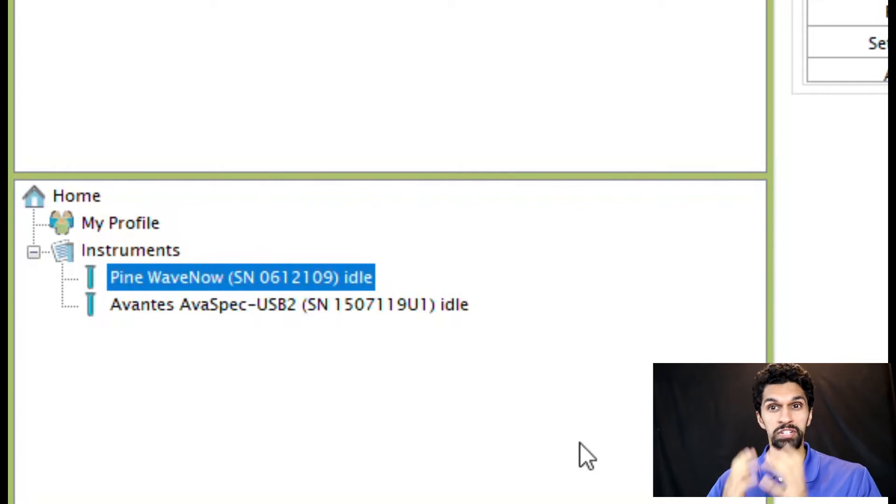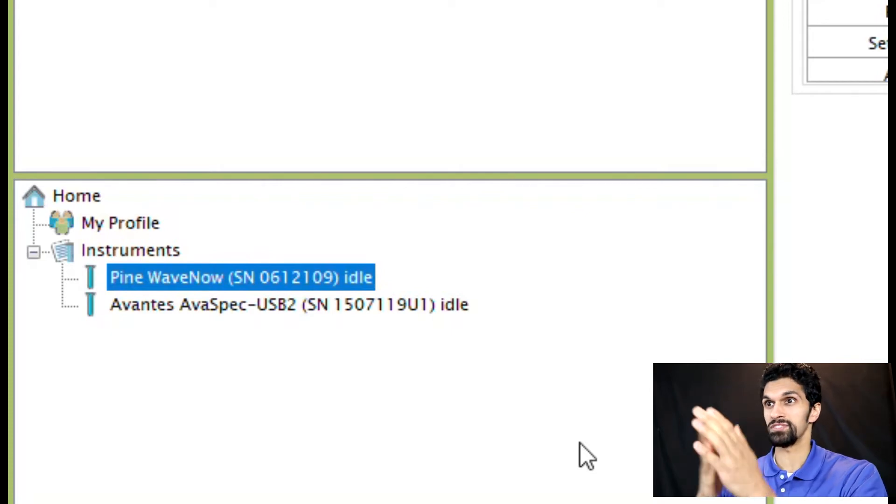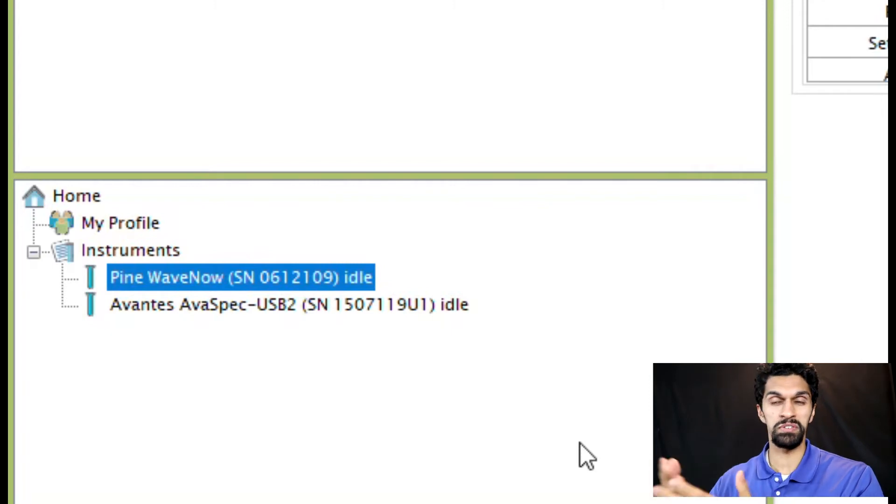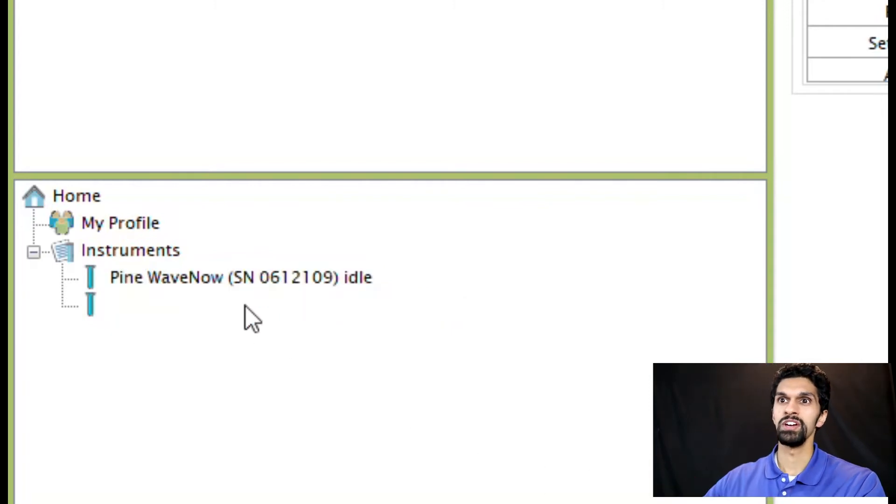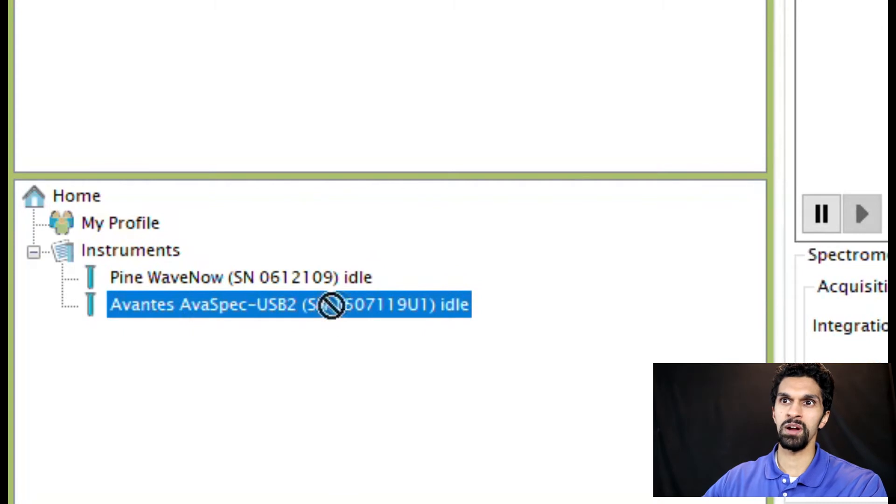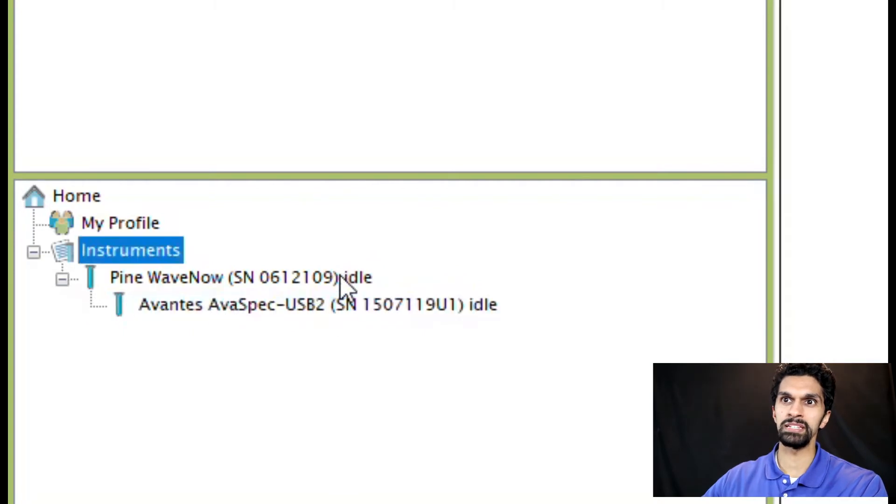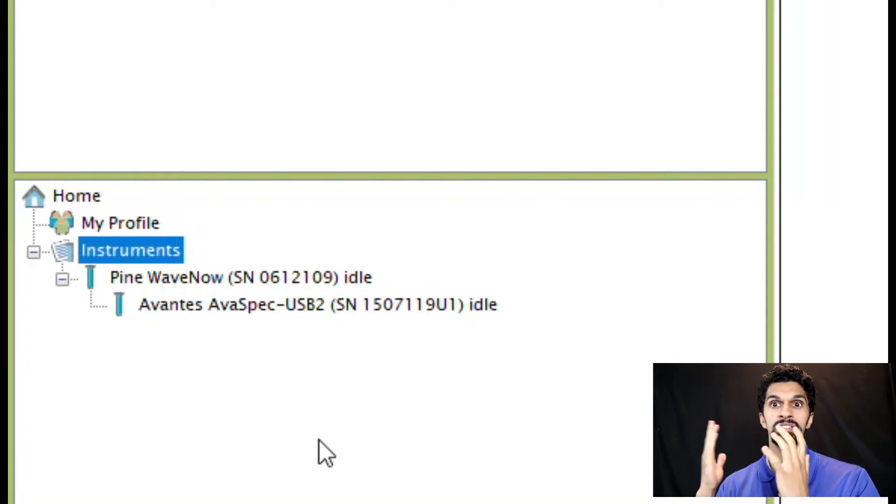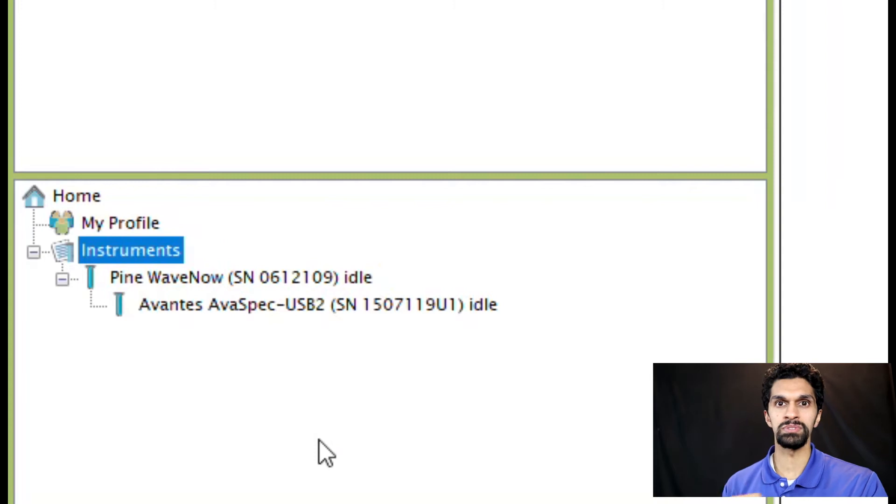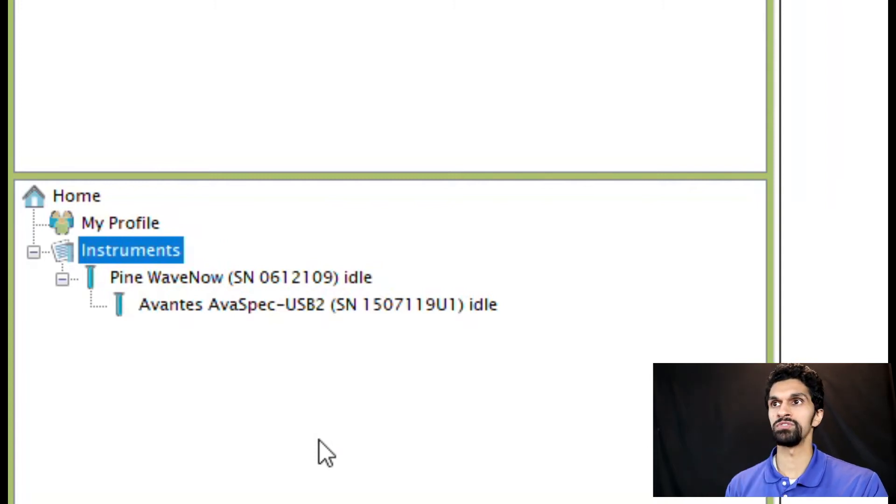I hope you don't have that kind of dinner conversation, but your instruments certainly don't have to. If you go to the lower left hand corner it's very easy to correct this. You simply need to select the Avantes spectrometer and then drag and drop it into the potentiostat. Now you'll see those two instruments are nested. The Avantes spectrometer is nested into the WaveNow potentiostat and those two are communicating with each other via software.